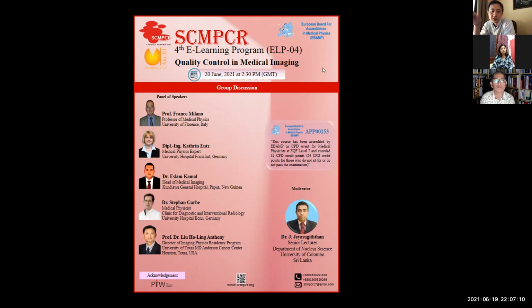Many of the MRI used for radiation therapy use a 3D image. You want to make sure the 3D distortion correction is turned on instead of 2D only. So distortion correction is very important. The bandwidth covers the field homogeneity, which causes distortion, and the distortion correction covers the gradient related distortion.